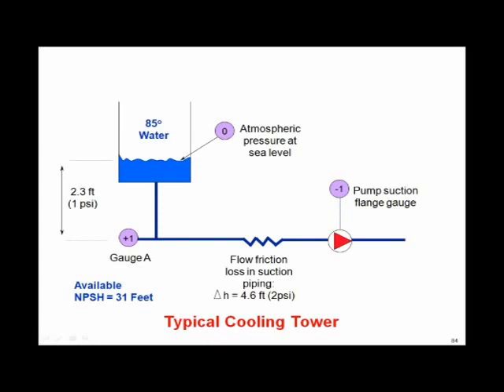So when I turn the pump on, my gauge on the suction side of my pump is going to become slightly negative. It's going to lose 2 pounds because of friction loss. So I had a positive pressure of 1 from the elevation. I lost 2 pounds running through the friction. So the suction gauge now reads a -1 if it's a compound gauge. So one of my pet peeves to everybody listening to this: make sure all your cooling towers have a compound gauge. It's not unusual for us to go on a job site and see the gauge read 0 because it's not compound, and yet it may actually have a negative pressure. People telling us the pressure is 0. Well, if it's not a compound gauge and you got a negative pressure, how are we going to know it? So first pet peeve, make sure.